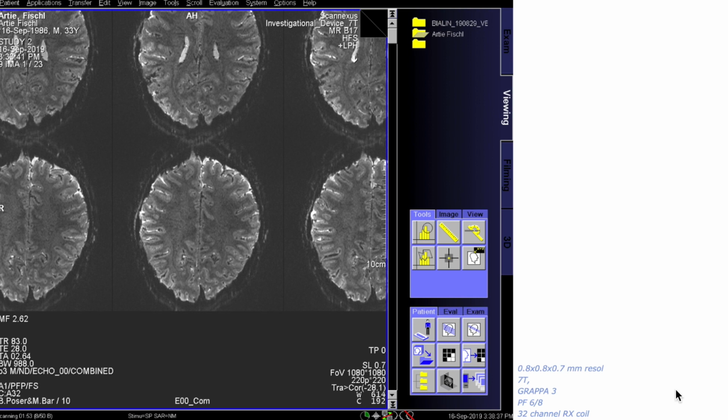And here on this slide, you can see the effect that changing this improved grappa parameter has on actual data. Here I'm flipping back and forth between the default and the improved grappa. You can see that it changes the weighting a bit, which doesn't really affect our fMRI signal a lot. As long as this weighting is constant, we usually only care about the temporal fluctuations.